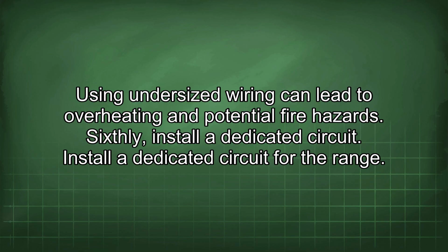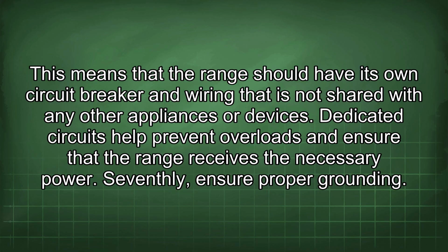Sixthly, install a dedicated circuit. Install a dedicated circuit for the range. This means that the range should have its own circuit breaker and wiring that is not shared with any other appliances or devices. Dedicated circuits help prevent overloads and ensure that the range receives the necessary power.